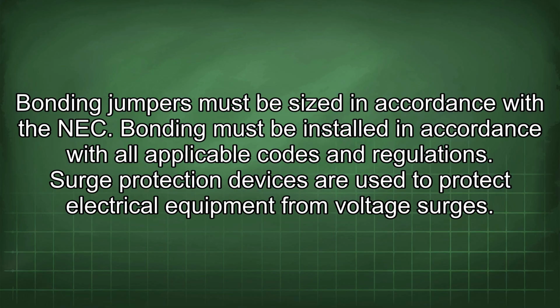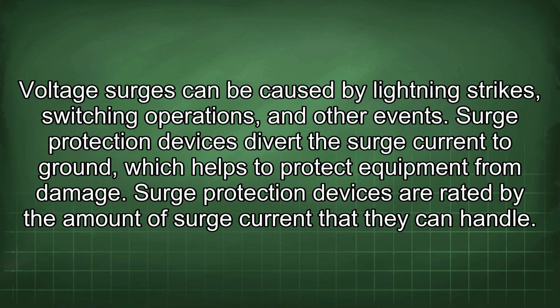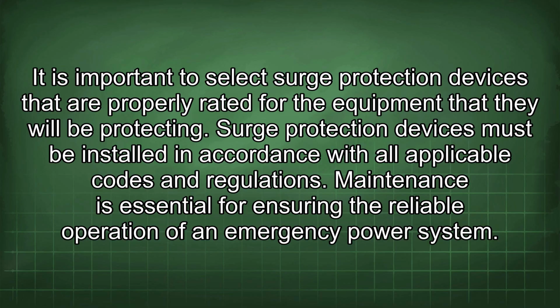Surge protection devices are used to protect electrical equipment from voltage surges. Voltage surges can be caused by lightning strikes, switching operations, and other events. Surge protection devices divert the surge current to ground, which helps to protect equipment from damage. Surge protection devices are rated by the amount of surge current that they can handle. It is important to select surge protection devices that are properly rated for the equipment that they will be protecting. Surge protection devices must be installed in accordance with all applicable codes and regulations.